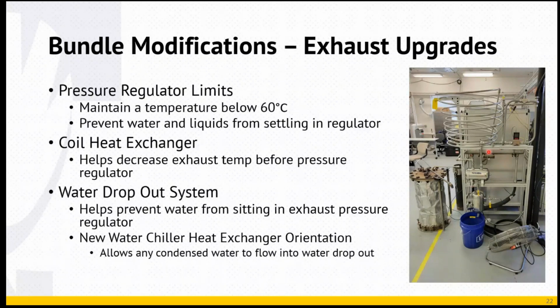This was also put on a slight slant so that if we condensed any water, it would flow into our water dropout system. This system is made up of two tanks, built in a way that we can take the water out even while at pressure, which is why there's a combination of tanks and valves there. Then it exhausted through the pressure regulator and out to the fume hood.